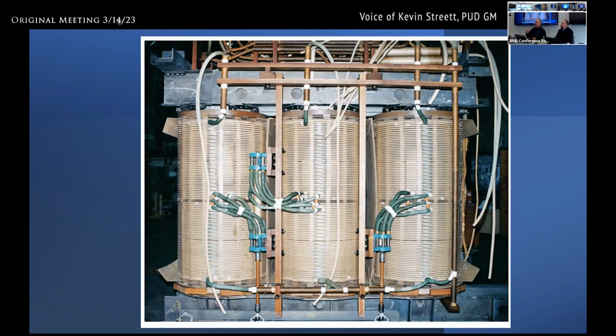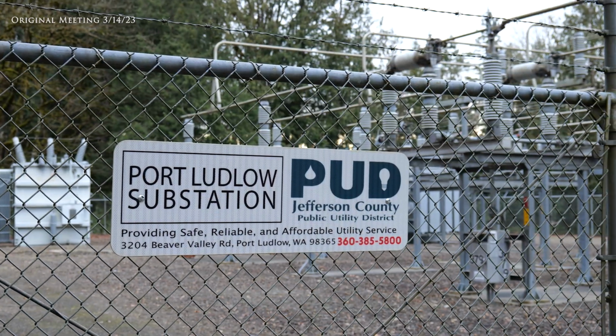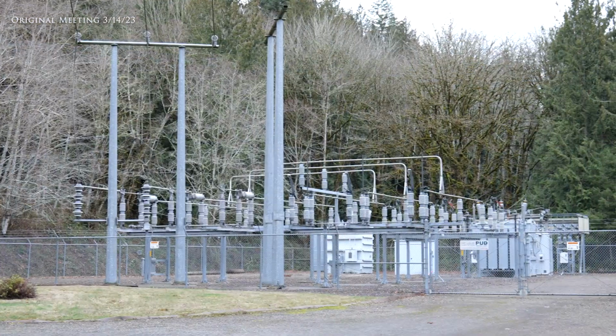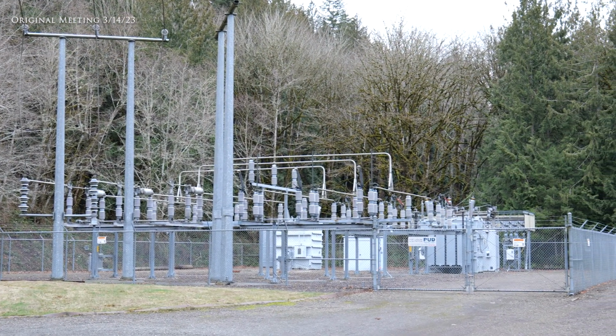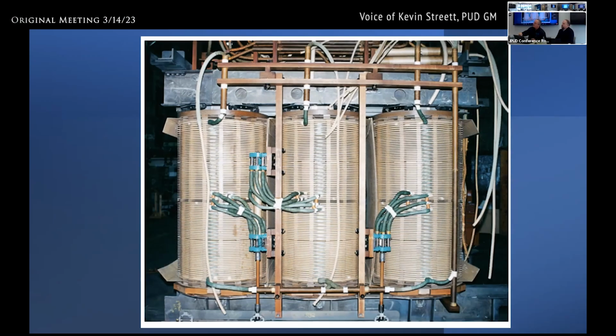Now, another component inside the transformer is a paper. There's a cellulose component to the paper that you can test in an oil sample to see if your paper is going bad. But what we feel happened with our transformer, specifically at Port Ludlow, is the winding shorted out. The windings will short between the gaps on the transformer core itself. So they'll be short across. This transformer did short in 2012, right before we purchased the system.